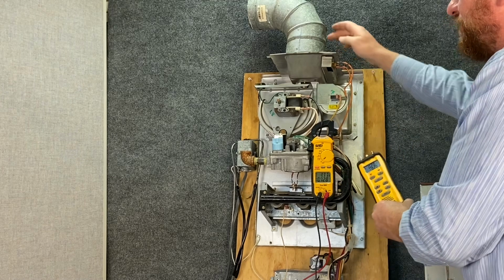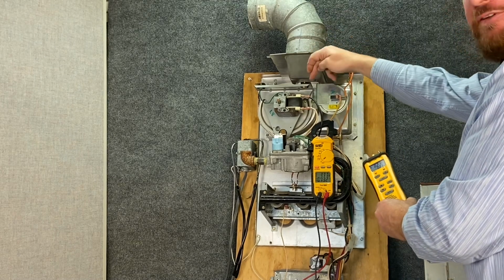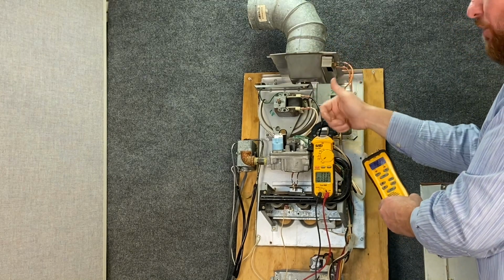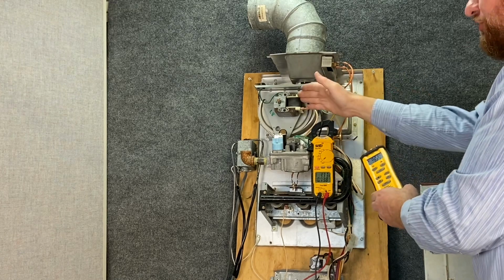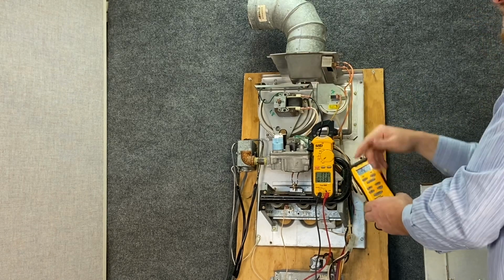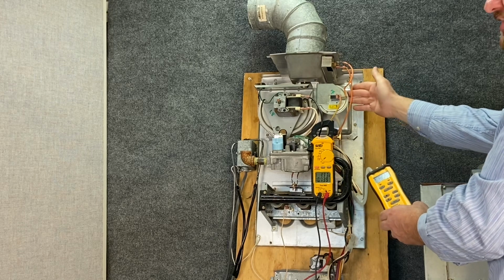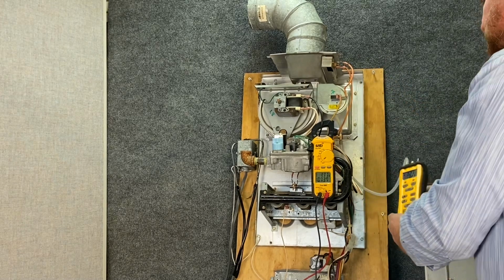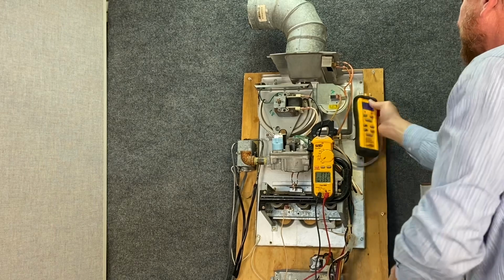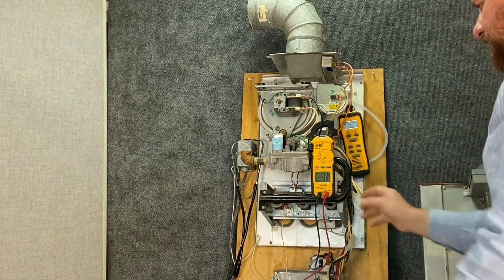The next thing I do is shut the system off, look inside the flue pipe to make sure that motor and that wheel is in good shape. So if the motor's in good shape and it's pulling the proper vacuum, your next step would be to check the pressure switch. You would check to see if it's open or closed. How we can check that very simply is with our meter.